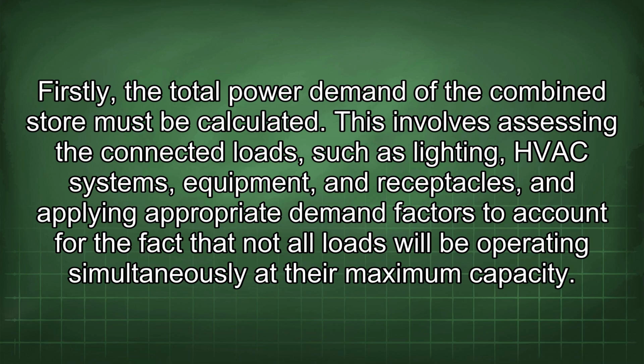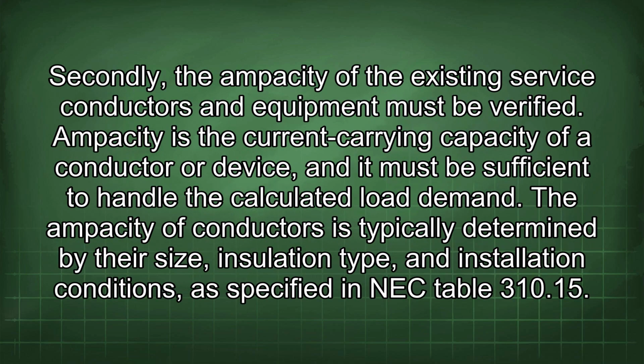This involves assessing the connected loads, such as lighting, HVAC systems, equipment, and receptacles, and applying appropriate demand factors to account for the fact that not all loads will be operating simultaneously at their maximum capacity. Secondly, the ampacity of the existing service conductors and equipment must be verified. Ampacity is the current carrying capacity of a conductor or device, and it must be sufficient to handle the calculated load demand.